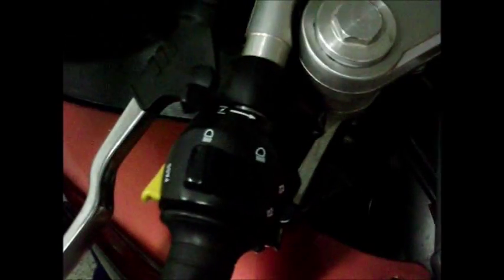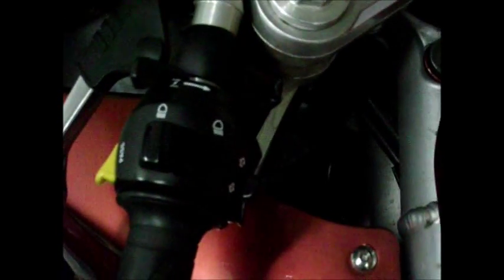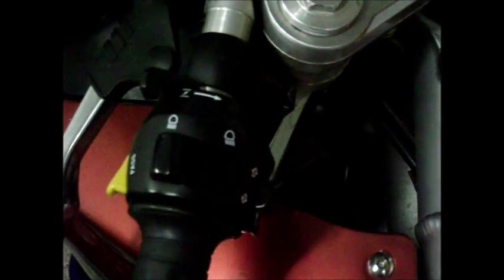I could do the same test across all the positive side of the circuit, measuring between, for example, the battery plus and the fuse box, and the on-off switch for the headlights, then the main low beam high beam switch. I could go probing all of those parts of the circuit to see where the voltage drop is most, and see if I could do anything to reduce it.